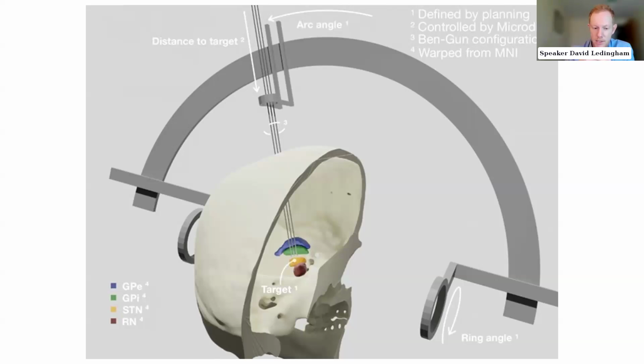The older devices may not be safe to have with an MRI. So it's really best to check with your DBS team what your device is capable of and what the precautions should be. But practically, new ones can probably have an MRI, but they might need a slight adjustment in their settings before and after, and a check before and after.